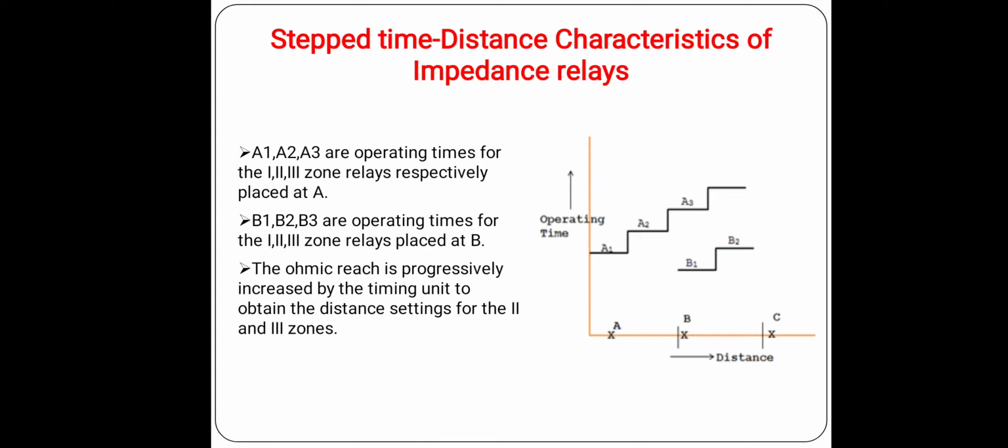That means if we are talking about the connections of impedance relay in case of three-step time protection, we need some directional relays with the connection of impedance relay with flags, timers and all the different types of things which we learned in higher studies, that is, the different types of connections of impedance relays. By employing these types of connections of impedance relay in our protective scheme, it covers all zones of protection, that means zone first, zone second and zone third of protection of the transmission line.